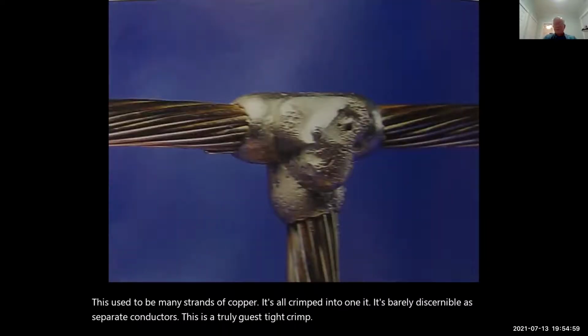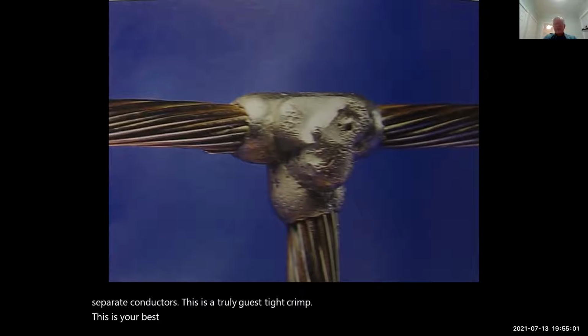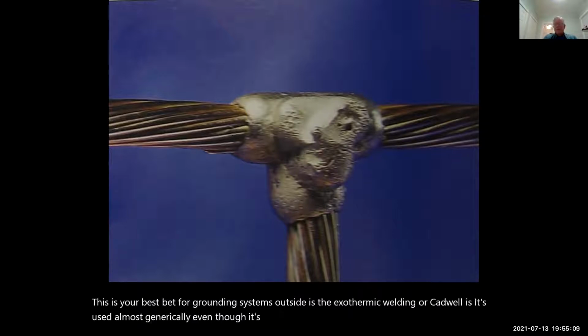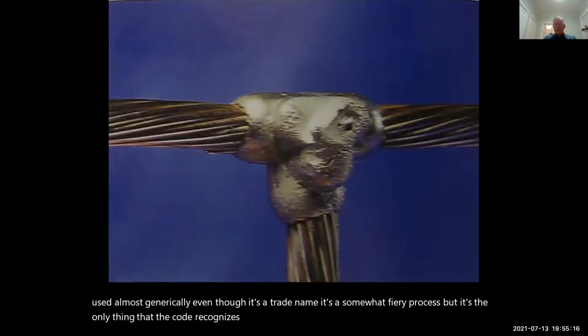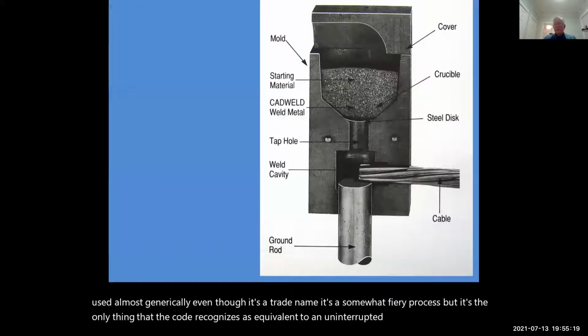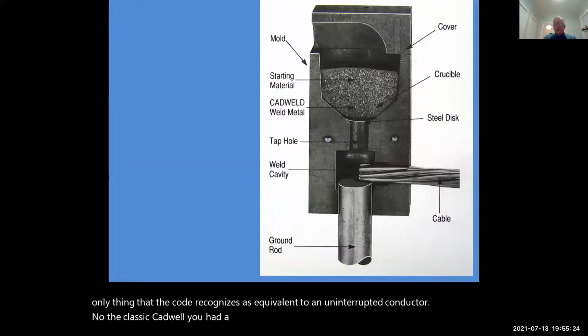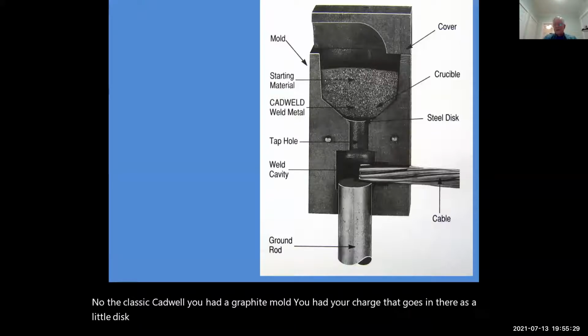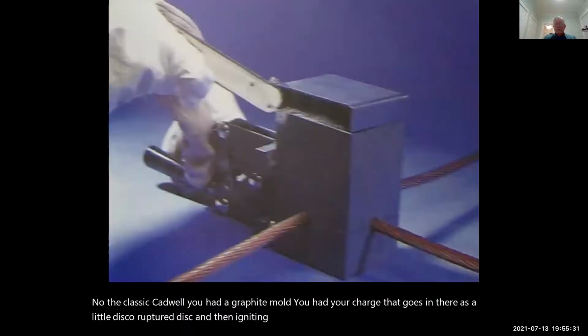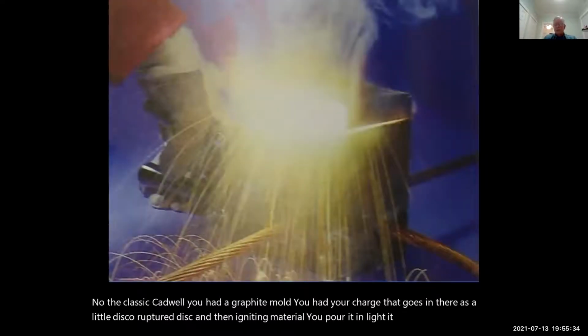This is your best bet for grounding systems outside, the exothermic welding or Cadweld, used almost generically, even though it's a trade name. It's a somewhat fiery process, but it's the only thing that the code recognizes as equivalent to an uninterrupted conductor. The classic Cadweld, you had a graphite mold, you had your charge that goes in there. There's a little ruptured disc, and then igniting material. You pour it in, light it, and send sparks all over.